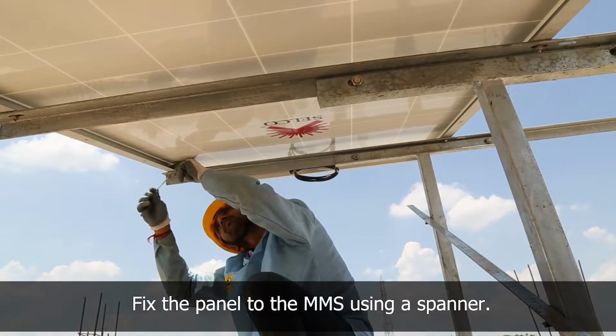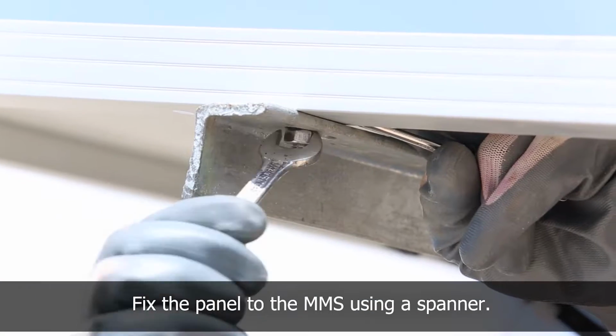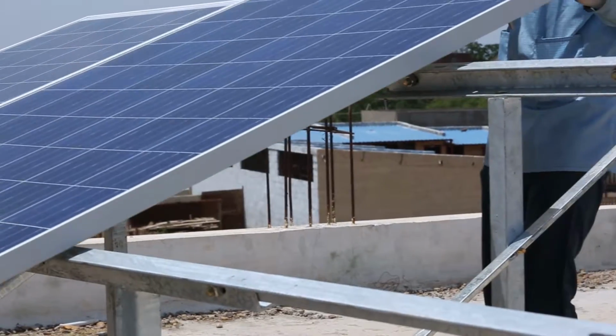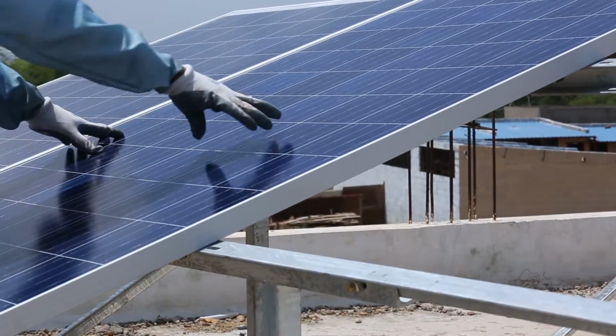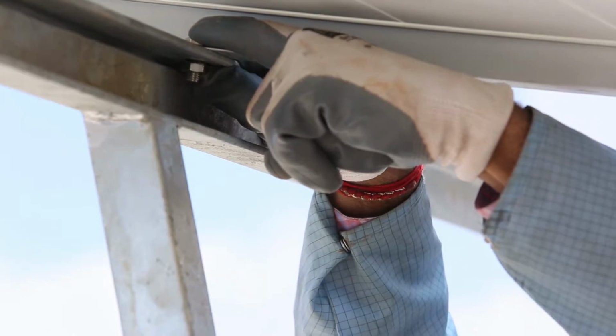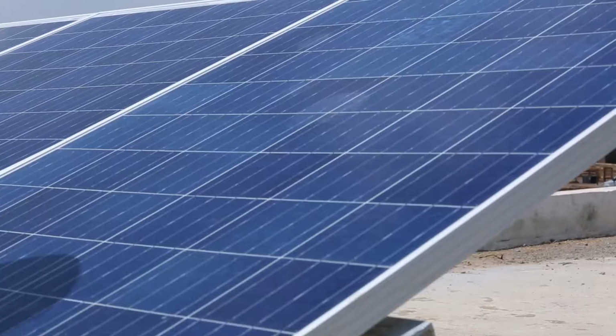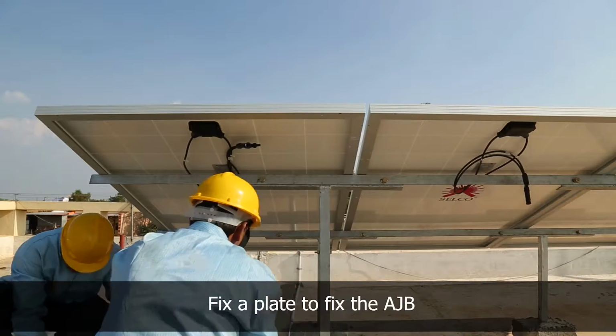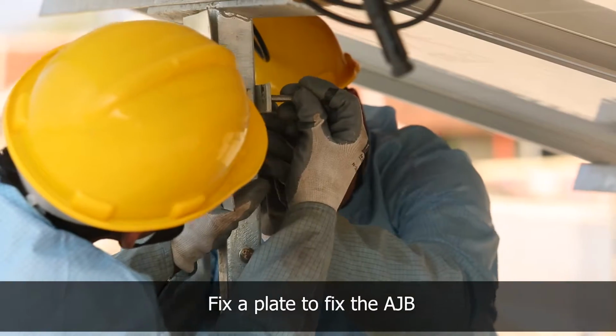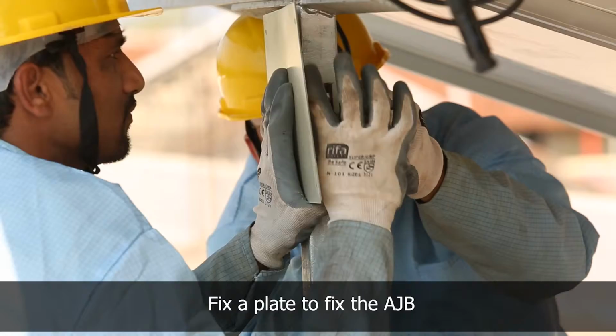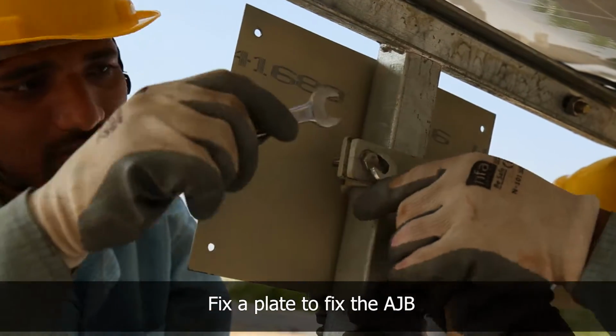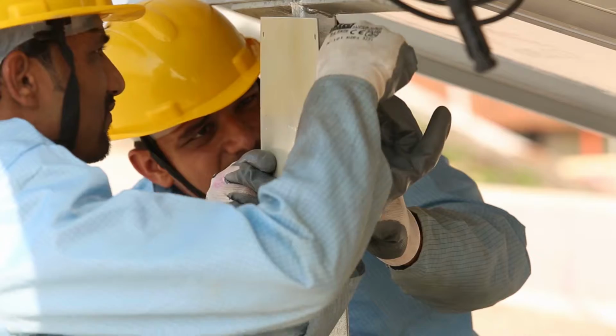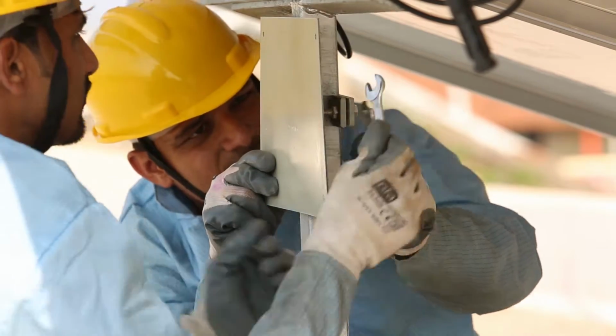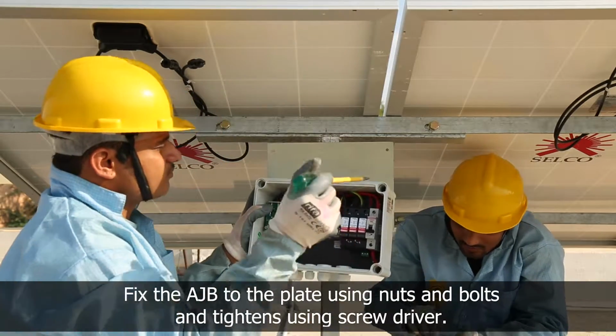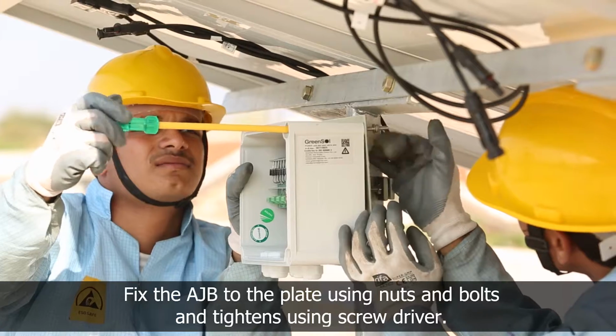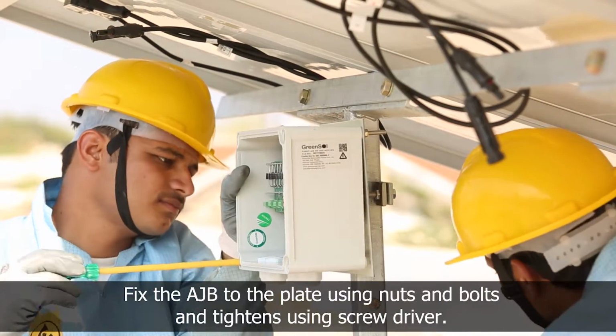Fix the panels to the module mounting structure using nuts and bolts and tighten using spanners. Fix a plate to fix the array junction box to one of the legs of the module mounting structure using nuts and bolts and tighten using 2 spanners. Fix the array junction box to the plate using nuts and bolts and tighten using a screwdriver.